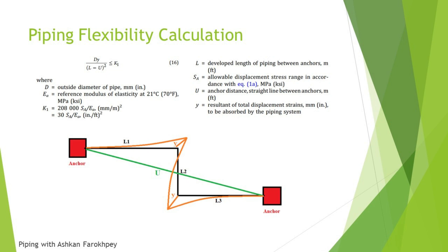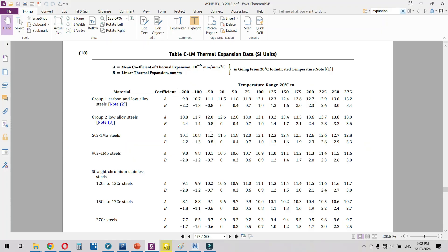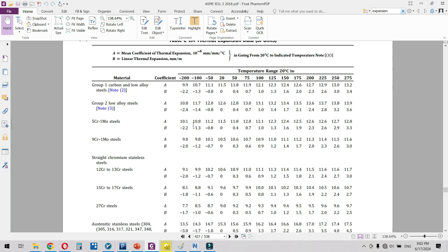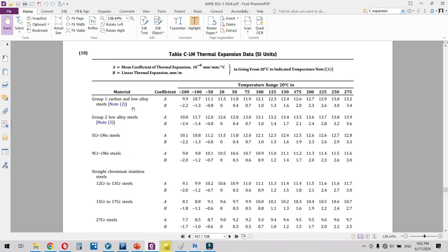Let's take a look at ASME B31.3 and let me show you the thermal expansion data in Table C1. As you can see in Table C1, we have the thermal expansion data of different materials, for example carbon and low alloy steels have different ranges of thermal expansion coefficient in different temperature ranges.